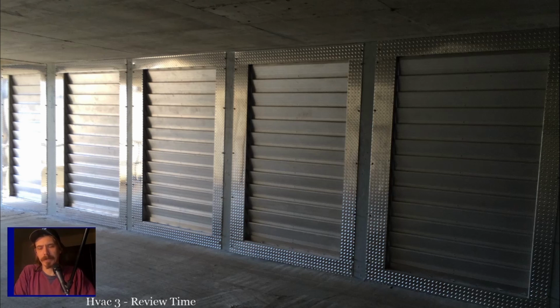What else in relays? They go through pressure switches in here, freeze stats. Again, I just think of all these things as switches. To me, a pressure switch, a freeze stat, an outdoor temperature thermostat, are just different ways of turning a switch on and off automatically. You just have to understand the temperatures or the pressures at which those operate so that you fully grasp their operation. Furnace fan controls are basically just time delays.